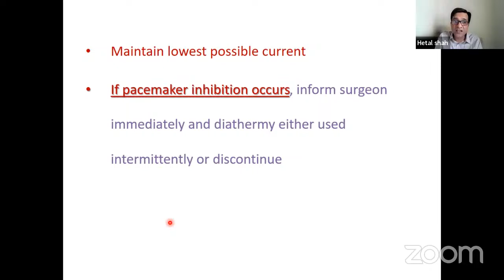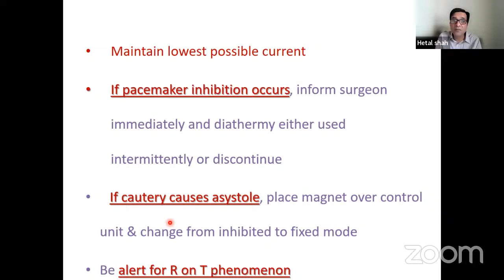If pacemaker inhibition occurs, if you see it from the ECG, inform the surgeon immediately and diathermy should be discontinued immediately. If cautery causes asystole, you place a magnet over the control unit and change from inhibited to the fixed mode so that at least some rhythm will start, and maybe you need to resuscitate those patients, right? And be alert, as the R-on-T phenomenon with the cautery is possible.